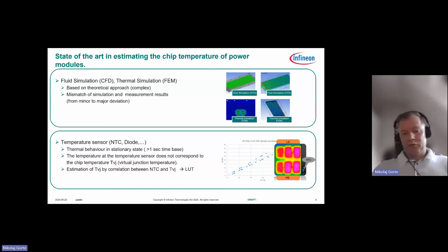The thermocouple method is used to validate the thermal inverter simulation. In this case, it is also important that the power module and the thermocouples are in steady state, otherwise the measurement results will not correspond to the true chip temperature.